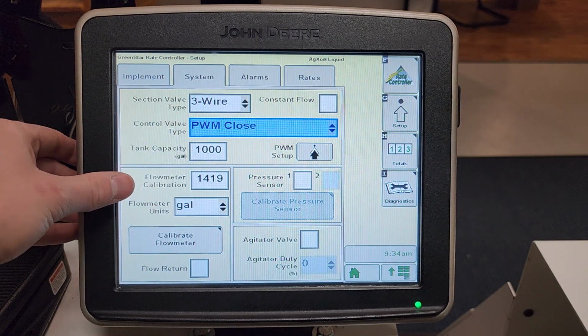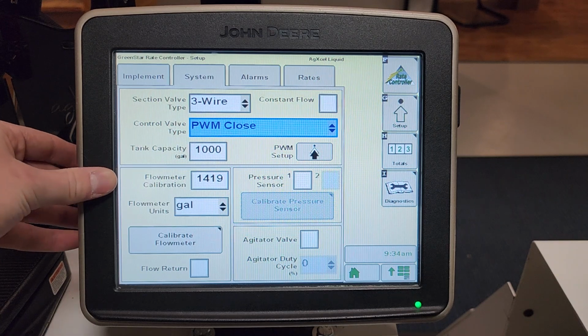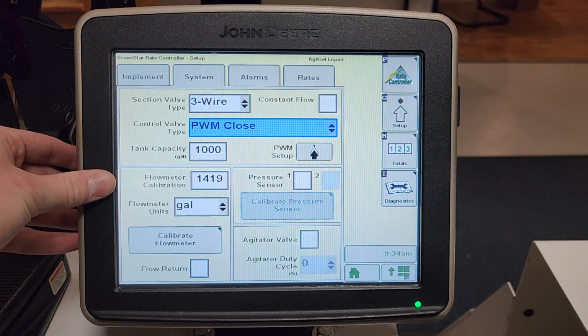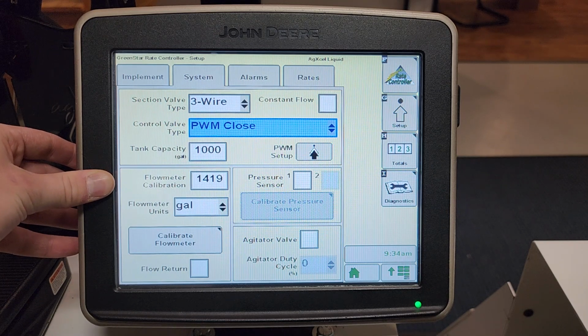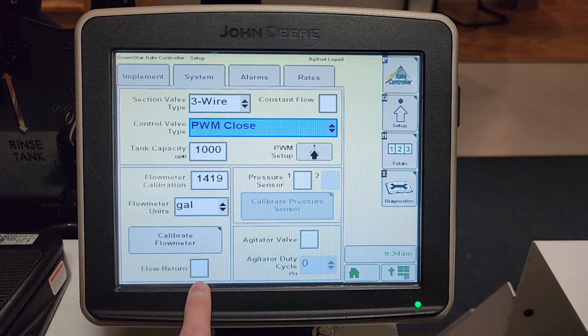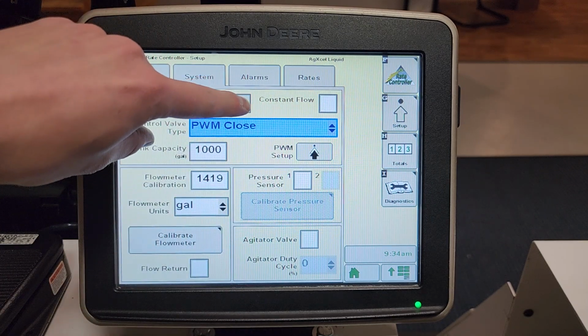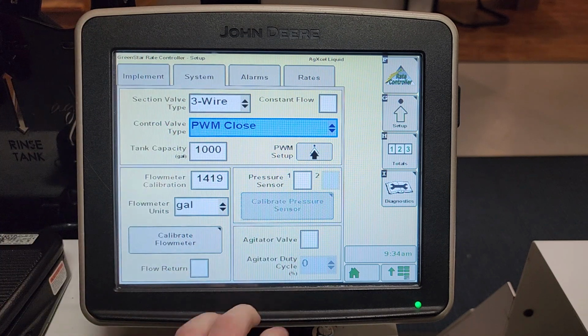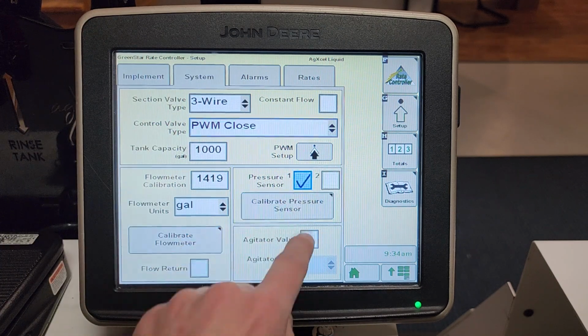You do not have to change your flow calibration number based off of the product you're using. So if there's a viscosity change, so if you're using some sort of thicker biological product versus water, you do not have to recalibrate your flow meter. Your flow return will not be checked, and your constant flow will not be checked. If you are using a pressure sensor, then you can set that up.